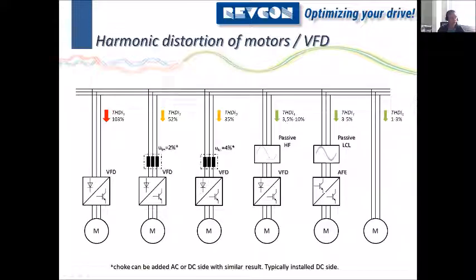Okay, that's for no inductance inside the drive. The next part would be a small inductance, a 2% inductance, which is quite small. You would reach a THDI of roughly 50%. In this example, the choke is placed outside the drive, but the position of the choke is not that essential. It can be AC side, it can be DC side. Typically it's placed DC side because that gives you some benefits in the production and you can use a smaller choke to reach the same performance.